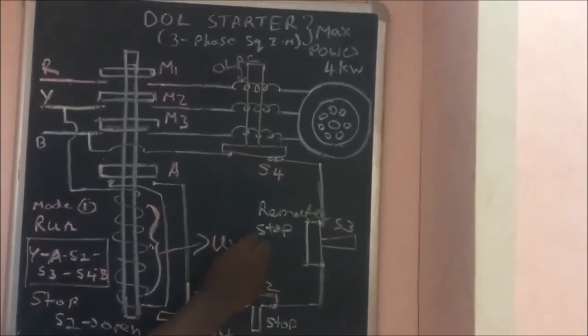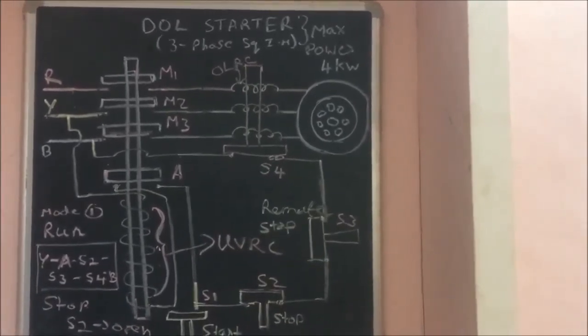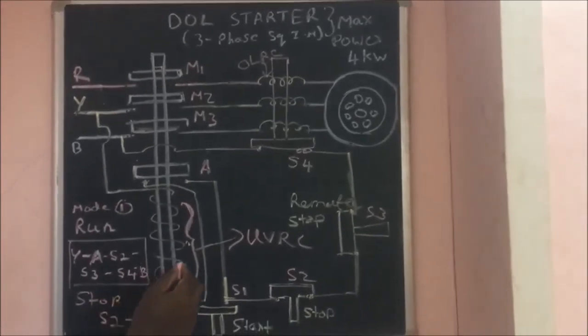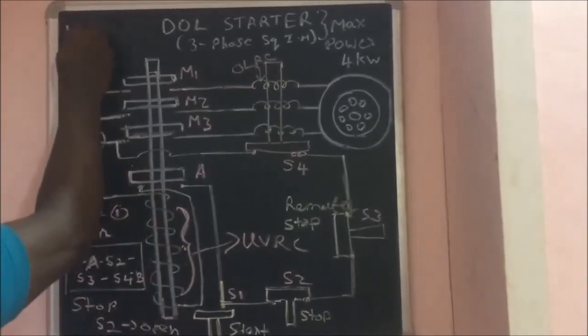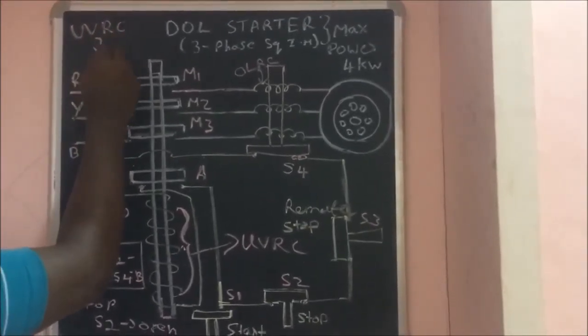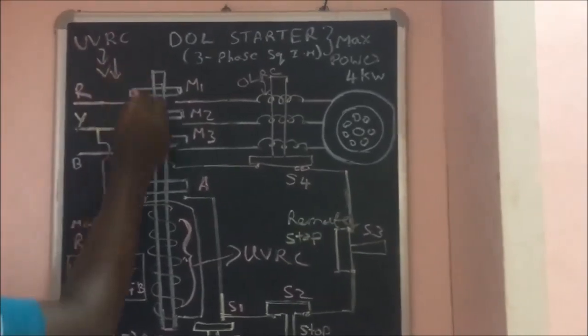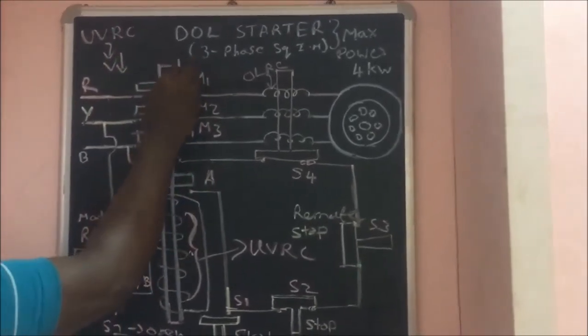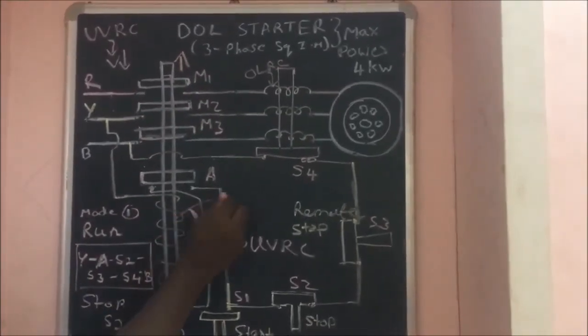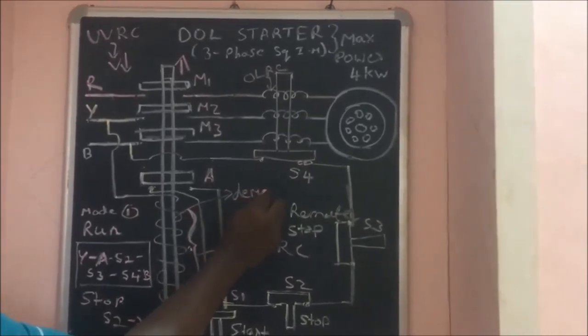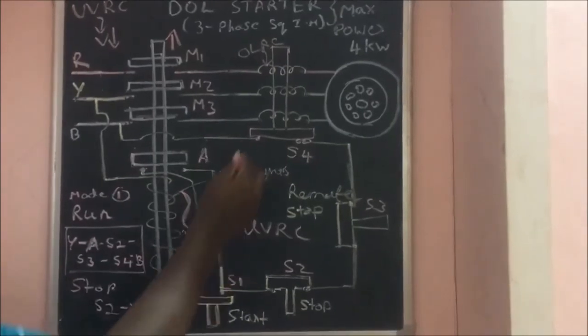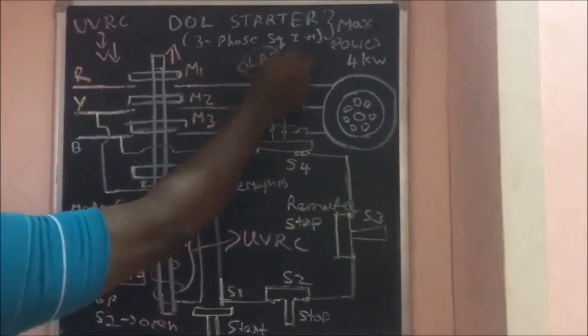When the under-voltage coil is magnetized, the nearby iron rod gets attracted. M1, M2, M3 conductors will close, current flows to the motor, and the motor starts rotating in running condition. Now S1 switch goes back to its original open condition, but current continues to flow through B-phase conductor via S2, S3, S4. The under-voltage release coil remains magnetized and the motor runs continuously even after releasing the green button.